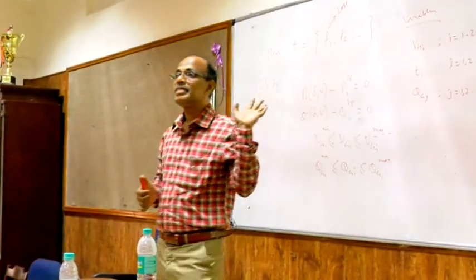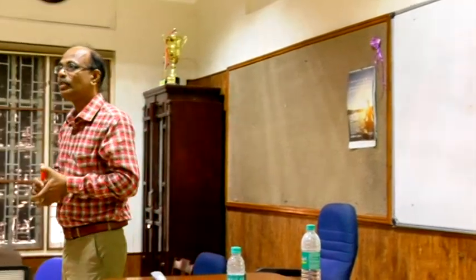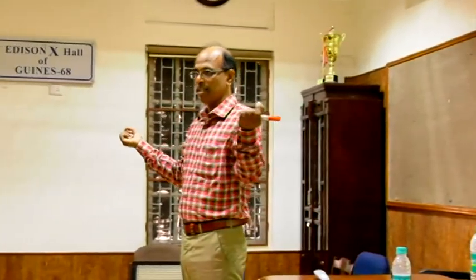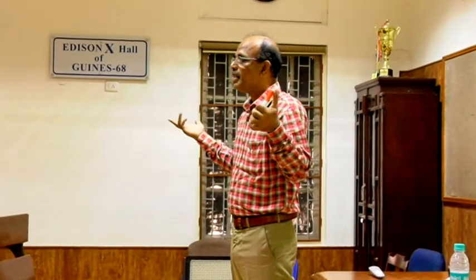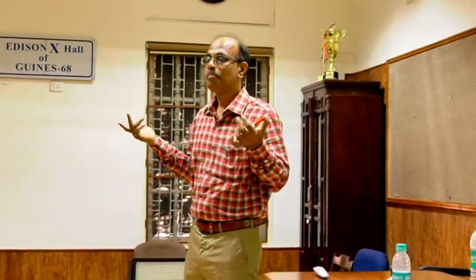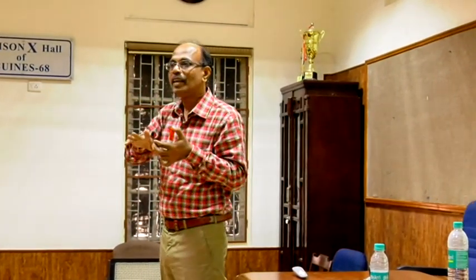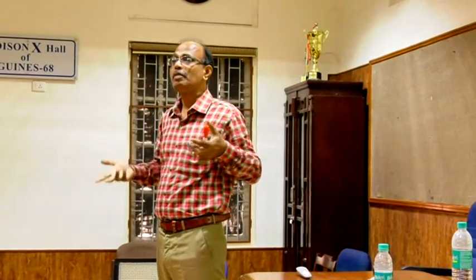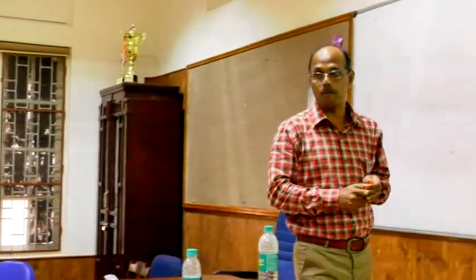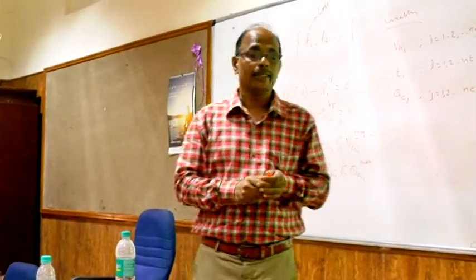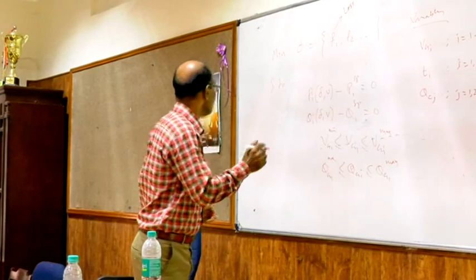Here the problem is reactive power. Before that, I would like to discuss the difference between real power and reactive power. What is the difference? Real power - it's very difficult to generate, very very difficult. But we can easily transmit real power from one point to another. Reactive power can be easily generated - even at this point, if you connect a capacitor bank, that will generate reactive power. But it is very difficult to transport reactive power from one place to another. That's why it is recommended to connect reactive power sources at load points.